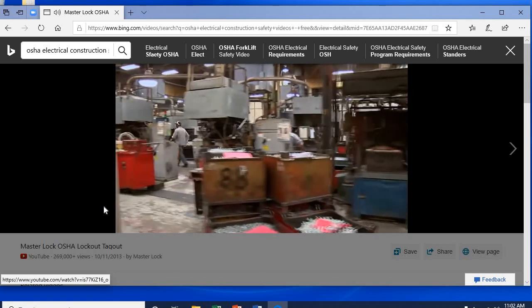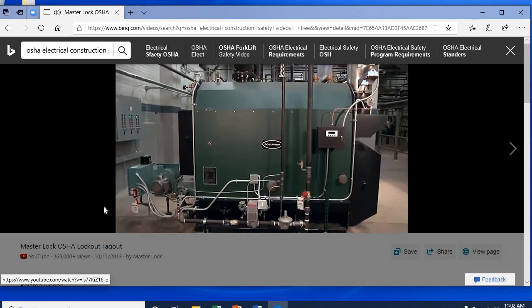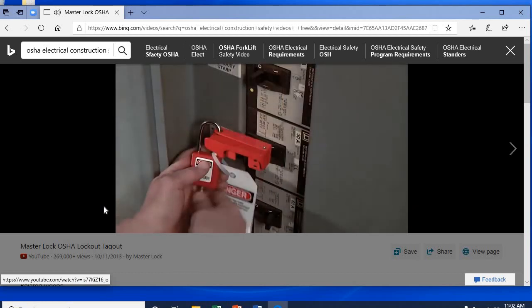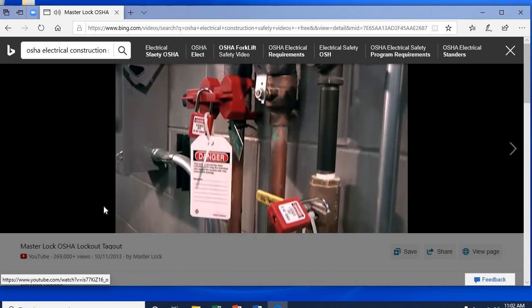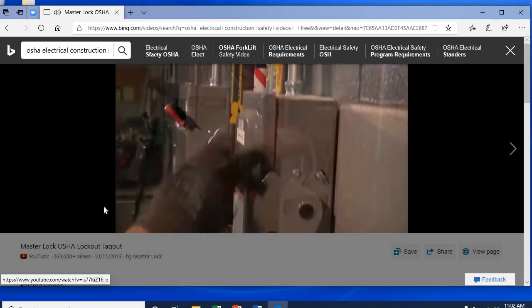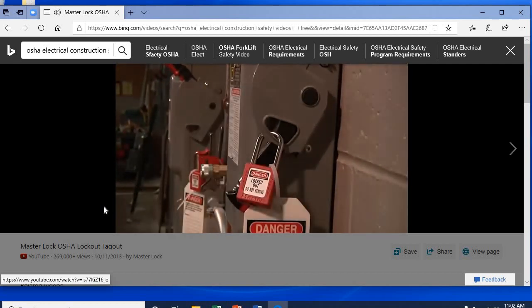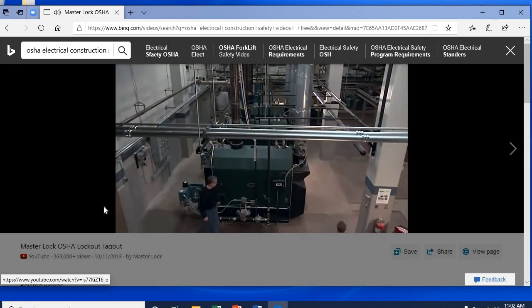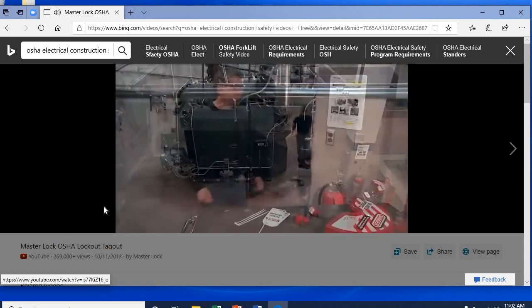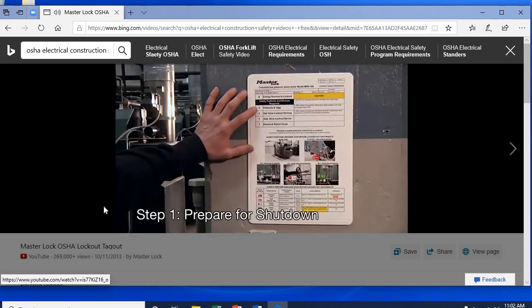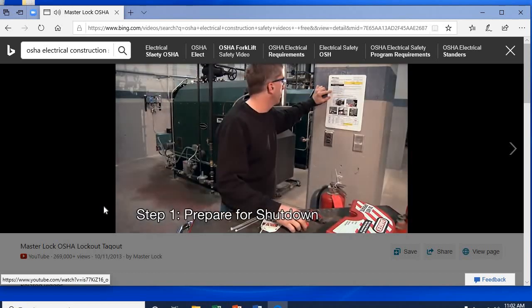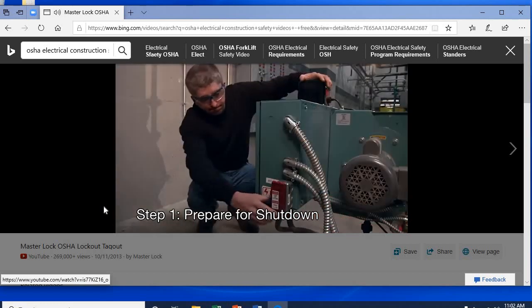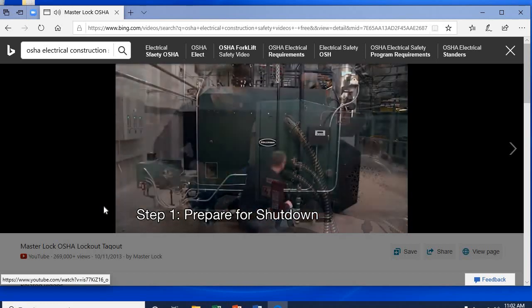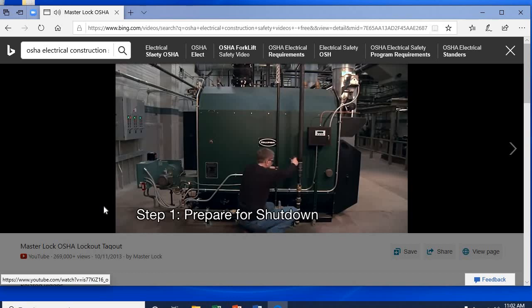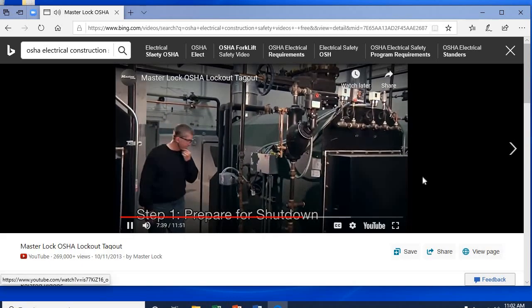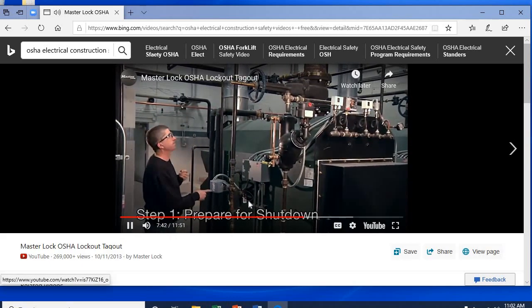Every piece of equipment must have its own particular procedure for lockout. It may mean locking out a circuit breaker, locking a valve in the off position, or using a disconnect switch, to name a few. In general, there are 7 steps for safe lockout-tagout. First, prepare for shutdown. Locate all the energy sources that power the equipment. Each source is identified on the machine's lockout procedure.